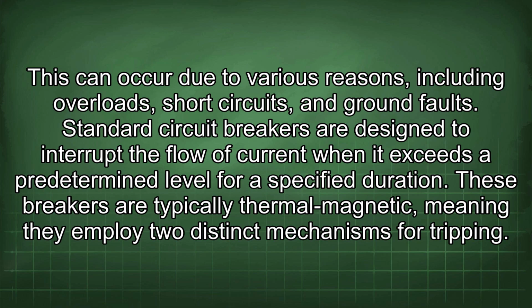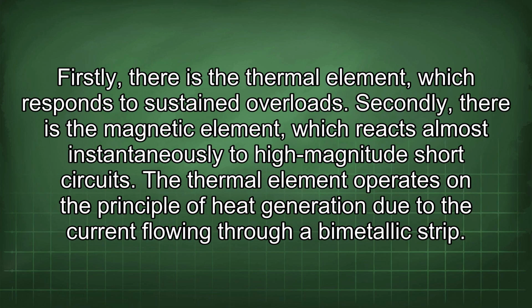Standard circuit breakers are designed to interrupt the flow of current when it exceeds a predetermined level for a specified duration. These breakers are typically thermal magnetic, meaning they employ two distinct mechanisms for tripping. Firstly, there is the thermal element, which responds to sustained overloads. Secondly, there is the magnetic element, which reacts almost instantaneously to high magnitude short circuits.